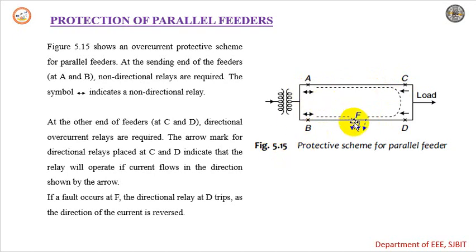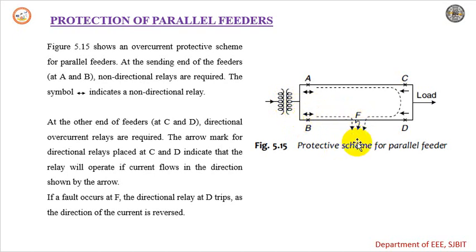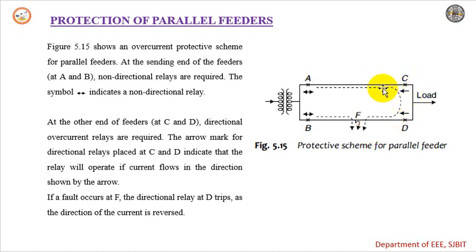Let us consider if there is a fault on feeder BD. When the fault occurs, the current will flow towards the faulty part. Since we are using a non-directional relay at B, the current flows to the faulty part. The current is also flowing in A, which is non-directional, and in C as well. But since the current is flowing in the normal direction at C, C will not trip.